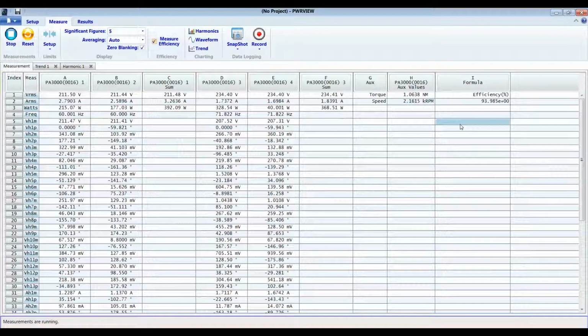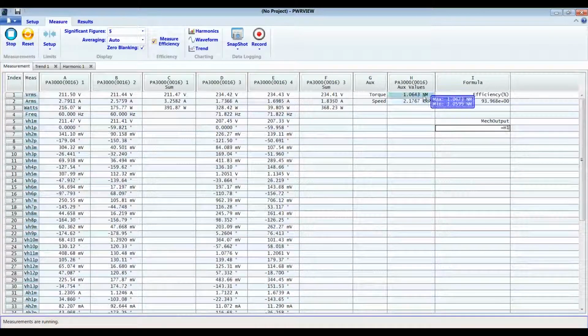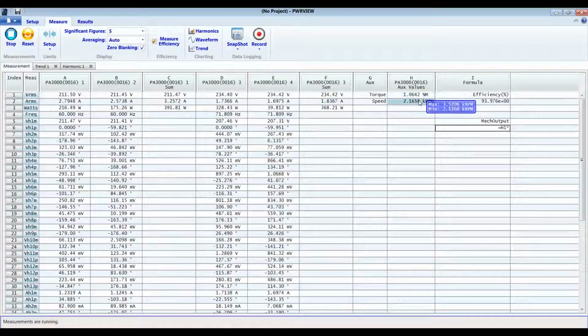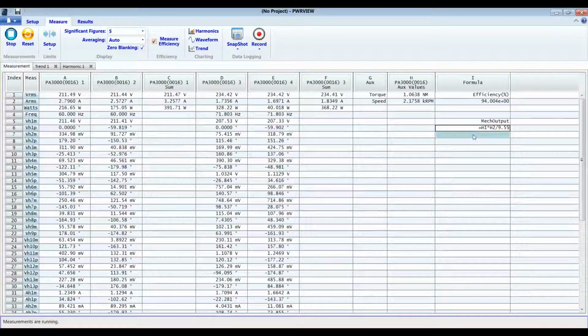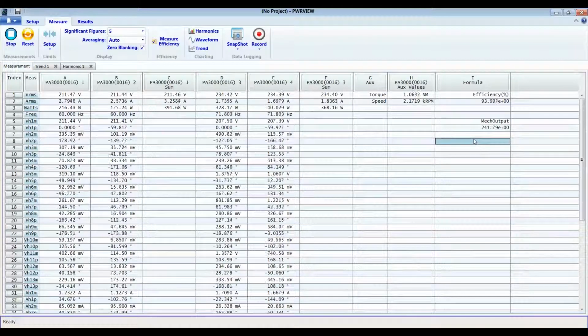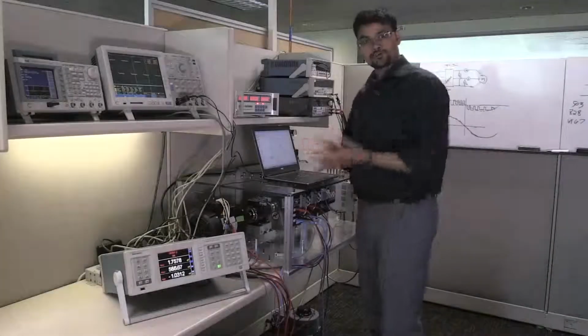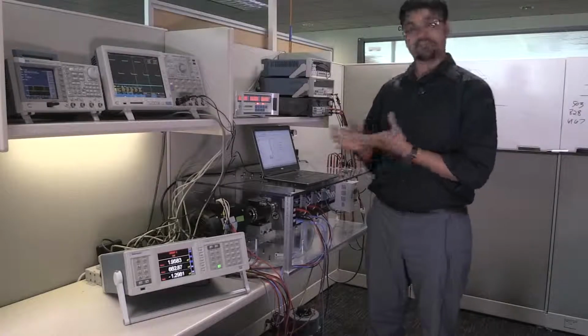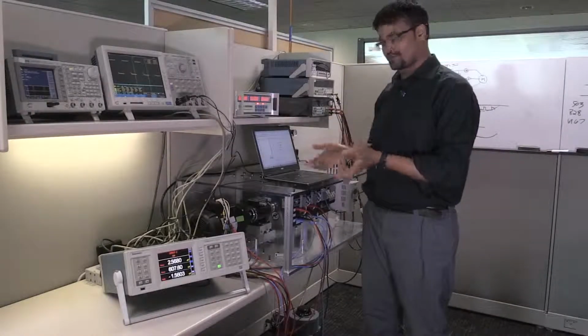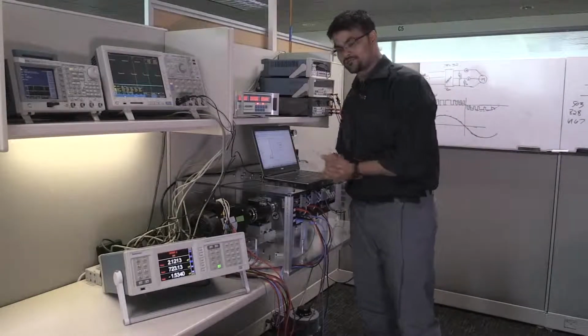Now, we can also calculate mechanical power output by entering the formula here in the formula column, right? So for a motor drive, it will be torque times speed divided by 9.55 or whatever your system is, right? Now, this will give us the mechanical power output, and you can use this output to eventually measure efficiency. So you can input that formula again in the same column. Okay, so there you have it. That's how you measure efficiency on a 3-phase motor drive system, on a PWM motor drive system, right?